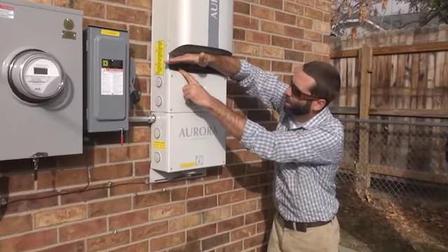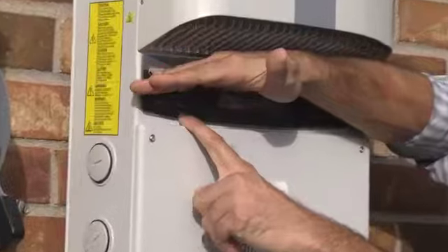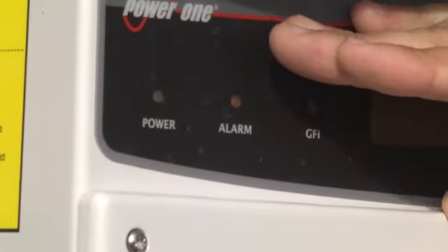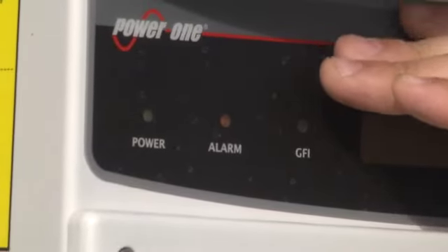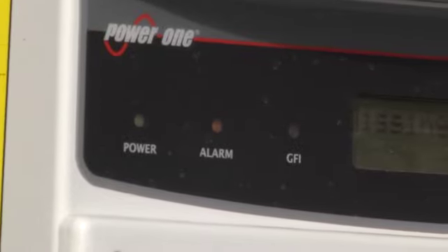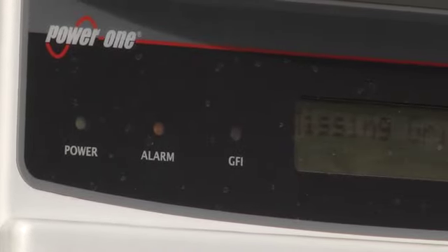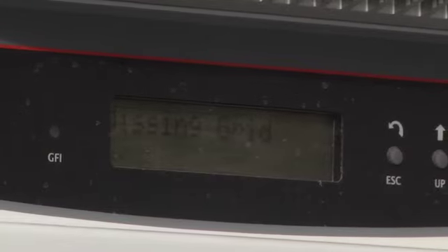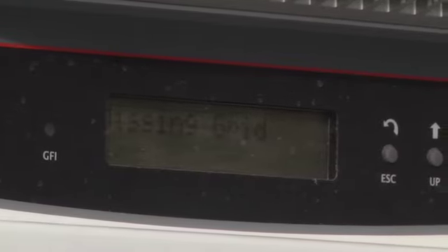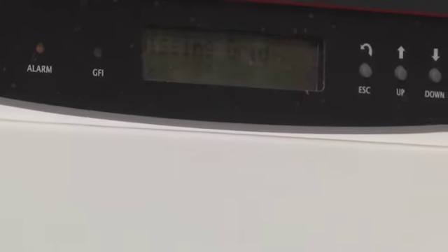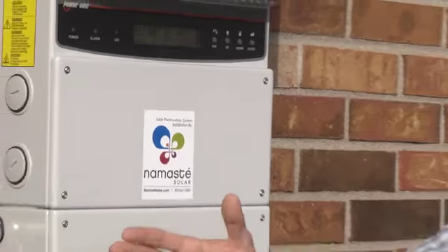There's also an alarm, the yellow alarm light is illuminated, and there is an error code that says missing grid. So as soon as the inverter loses the grid voltage for whatever reason, transformer blows, the whole grid goes down, or the AC disconnect is flipped, it notices that, it slams the door shut. So there's no electricity coming from the DC side to the AC side. So what then happens is the inverter just turns itself off and it won't turn itself back on until the grid voltage comes back on.